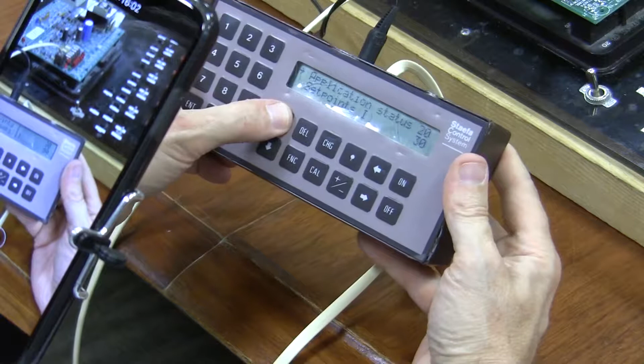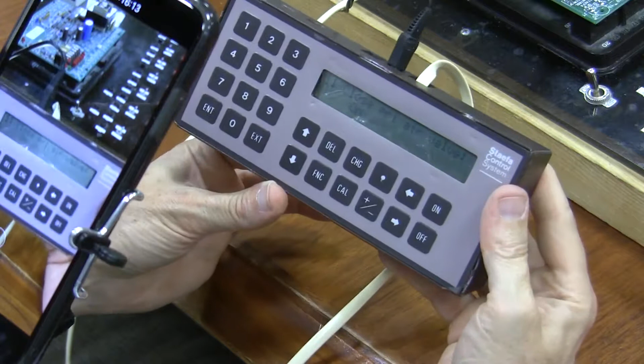Just for fun, if he's above set point, we would be trying to close the VAV box, right? So we're going to go back to the 10s, and I'm going to look at my outputs. Look at that. Open primary air valve is off. Closed primary air valve is on. See that? So the card's making sense, right?